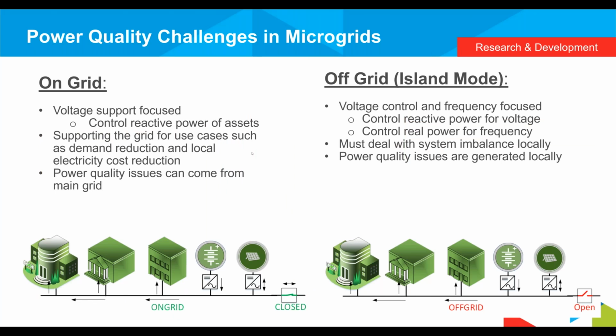So, power quality challenges in the microgrid. These are all things that need to be considered in order to define the controller for the microgrid. In this case, there's on-grid and off-grid. While the microgrid is on-grid, this is what it should be focused on: voltage support. It has to control reactive power assets in order to support the demands of the load in the smart homes, providing local support for the smart homes. It also has to support the grid for use cases such as demand reduction and local electricity cost reduction. So the microgrid has to be designed to use the different generation sources in order to reduce the cost of electricity locally. And finally, power quality issues can come from the grid, and the microgrid should be able to support the power quality locally.